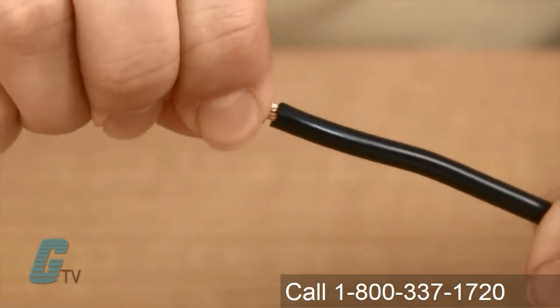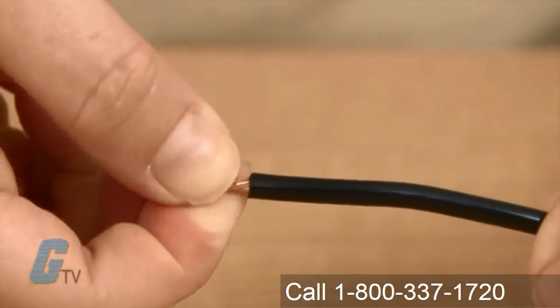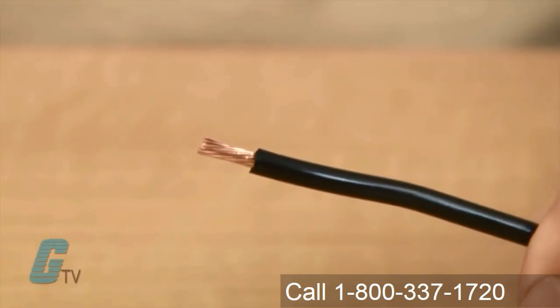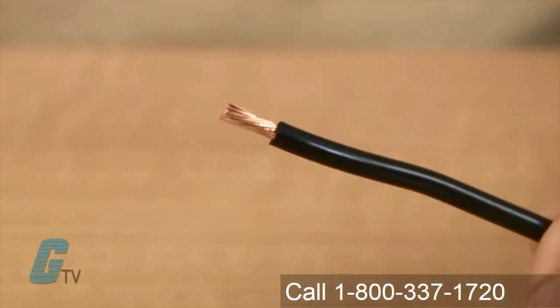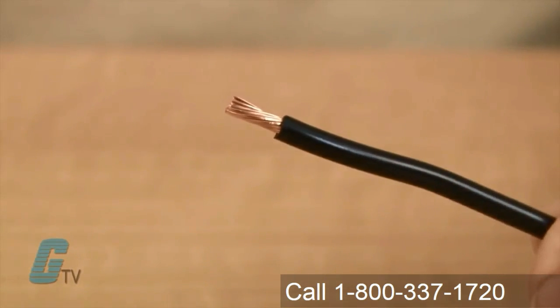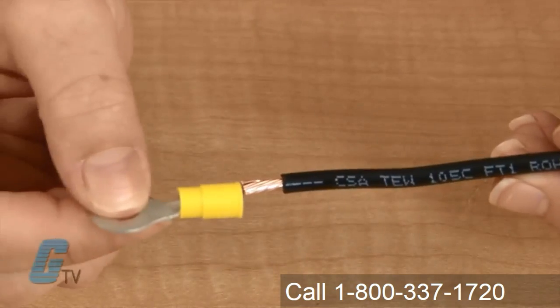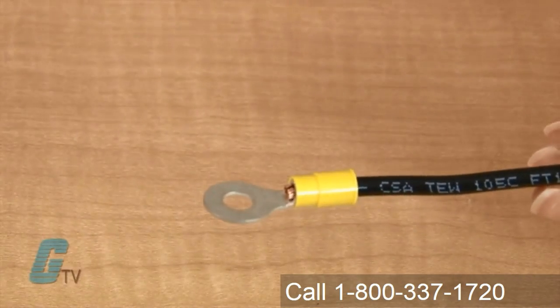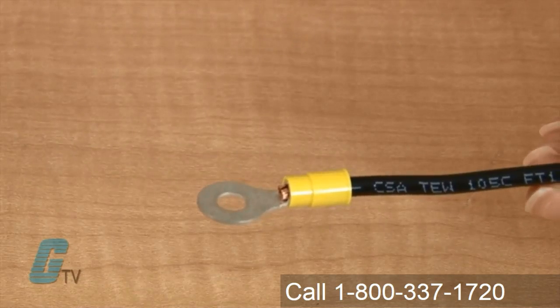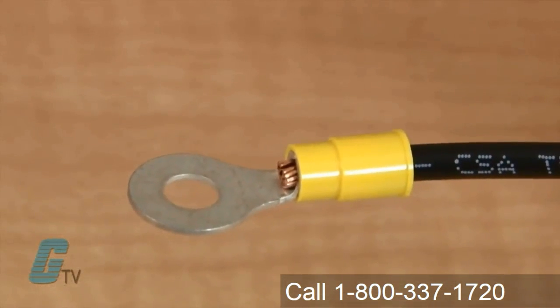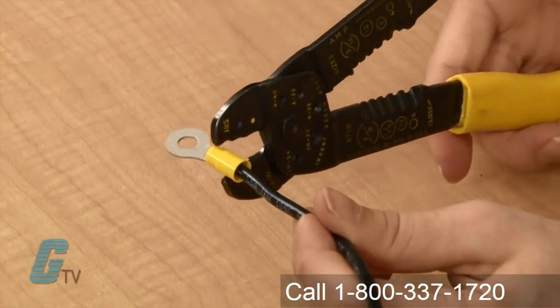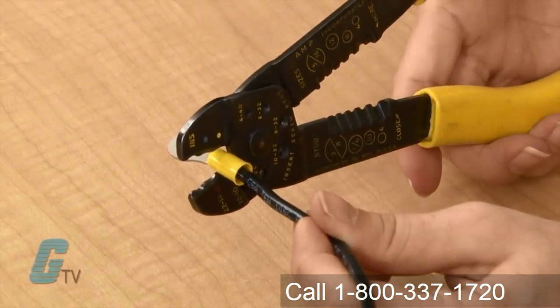Now that you have the end of the wire exposed, twist it with your thumb and finger to make the end more firm and to allow for a more positive connection for the connector. Proceed to insert the wire into the connector until the insulation on the wire touches the end of the barrel. Then insert the wire and terminal into the crimper.